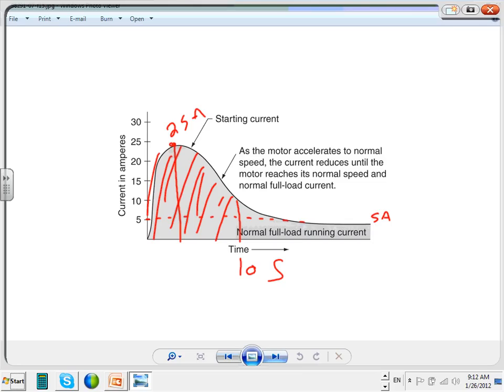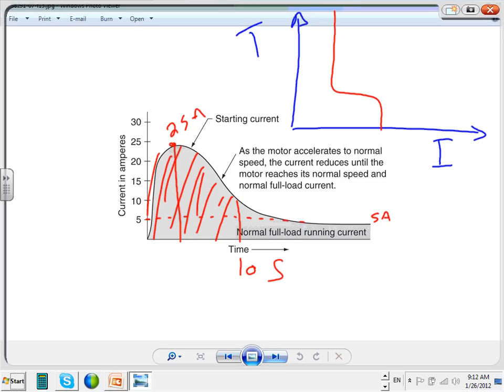Later on, and please remember that one because we're going to do short circuit coordination. When we move into next quarter, you and your friend Chad are going to be doing overcurrent coordination, where you're going to put the I, the current, here, and the time is here. And you guys are going to be drawing a curve that looks like this. Let's just use the same example that they're using here. Here's 5 amps, that's my 5 amps. This is my 25 amps. The same example except different parameters. And then you're going to have a fuse that sits right here to protect it.